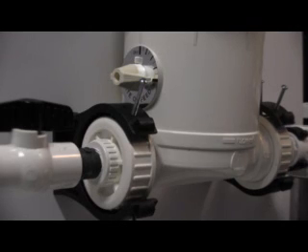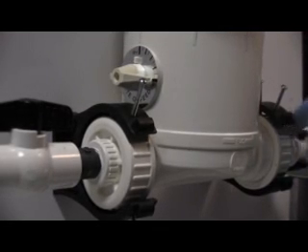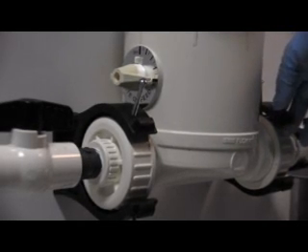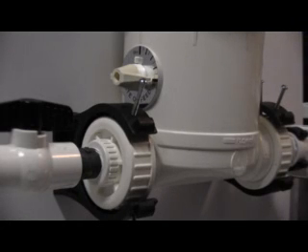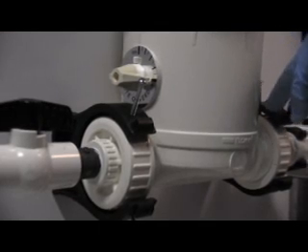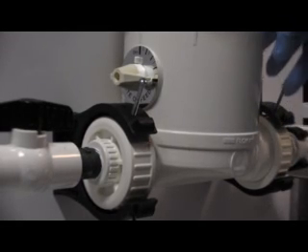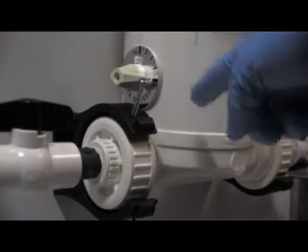But how about if I start to run this a distance? How about if I have a pipe on this side, on the outlet side, a pipe, and it goes 30 feet? Now we're starting to build pressure, okay? But what if that pipe leads into a bucket? Well, then you still will have a pressure drop, probably of over 20 psi, because you're going into a bucket. But what if that pipe that's 30 feet out is going into a spray cabinet? And the spray cabinet only has 2 nozzles. And those 2 nozzles are very small orifice nozzles. Guess what? Now my pressure has increased considerably, and that pressure increase considerably is going to affect the performance of this unit.